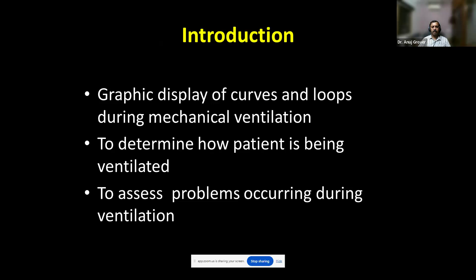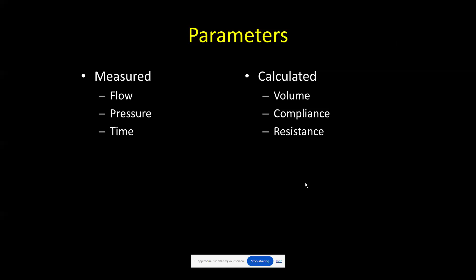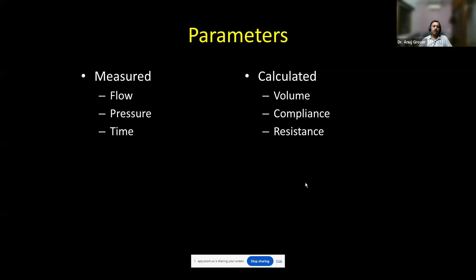Okay, so the flow, the pressure, and the time are measured, and from that information, the ventilator then calculates the volume, the compliance, and the resistance. And all these values are then displayed in a graphical information, and that's exactly what is pulmonary graphics. So the three measured parameters that you can see, the flow, pressure, and time, if you display them as curves, they are your scalars, and the volume and the compliance, those are part of your loops.